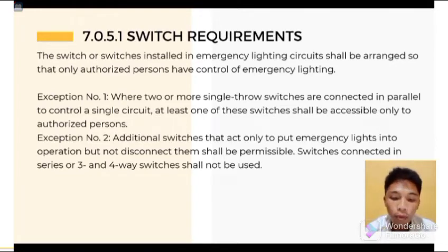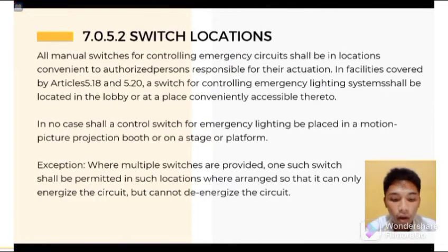Next is the 7.0.5.2 switch locations. All manual switches for controlling emergency circuits shall be in locations convenient to authorized persons responsible for their further actuation. In facilities covered by Articles 5.18 and 5.20, a switch for controlling emergency lighting systems shall be located in the lobby or at a place conveniently accessible thereto. So, in no case shall a control switch for emergency lighting be placed in a motion picture projection booth or on a stage or a platform. For this switch location to be accessible by the permitted person.